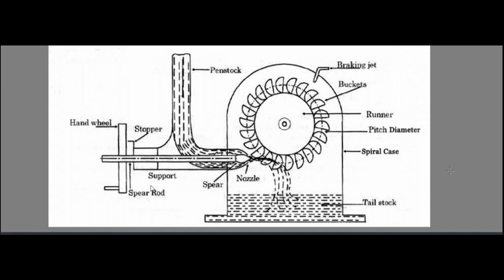Here you can see the penstock, and there is a spear to control the discharge. To control the flow, we have a change in pressure — a pressure hammer — which is handled with the surge tank. In a Pelton wheel, we don't have a draft tube, as the draft tube is associated only with reaction turbines.